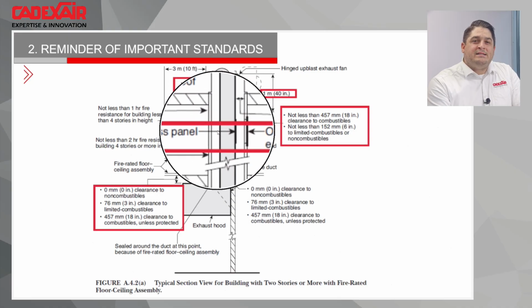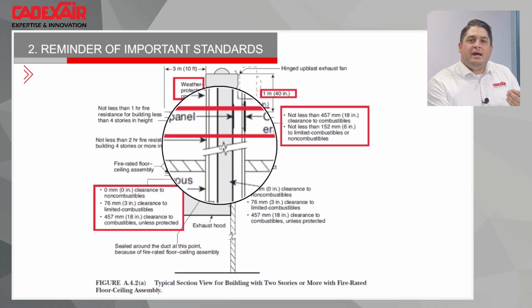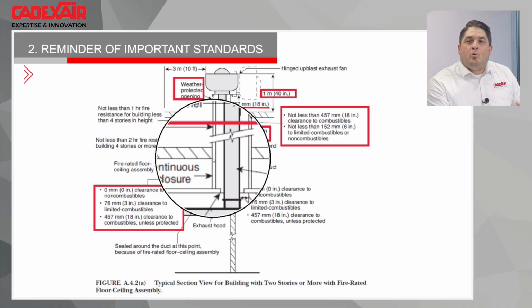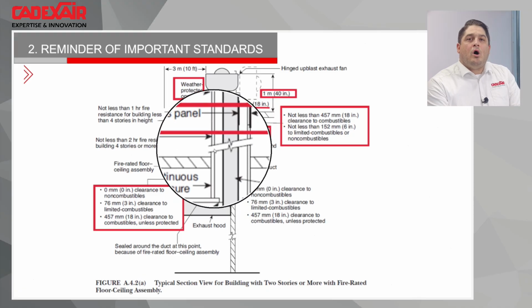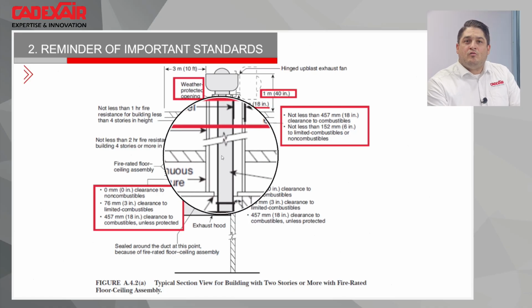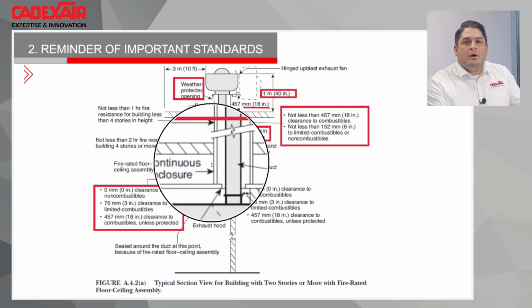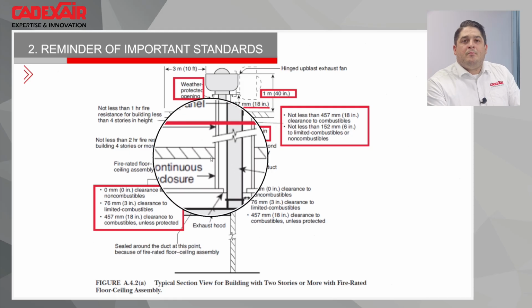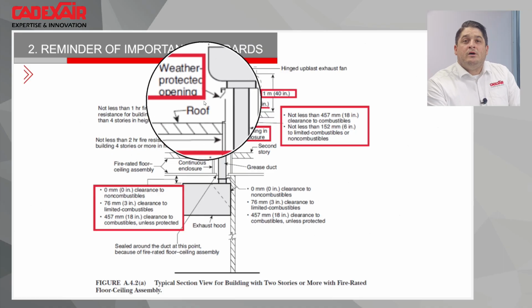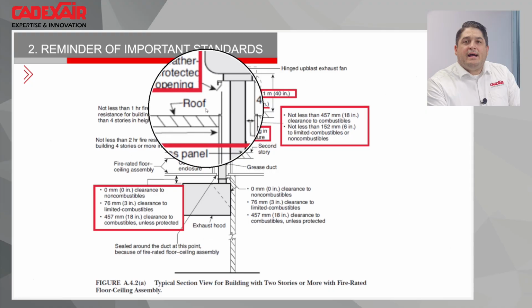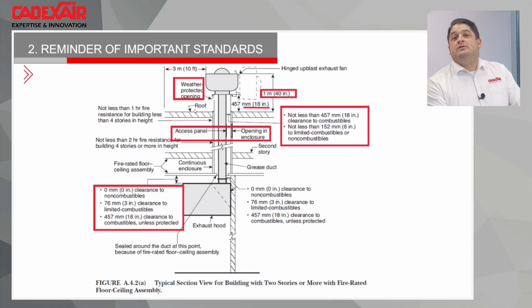The main reason why is that when you're in your shaft and sadly you have a big fire, the duct, with a bit of grease, gets hot, becoming red. So all the heat will dissipate inside the interstice between the ductwork and the fire enclosure. Normally the heat will go up and go up and go up, to the slab of the building. If it's really against the ductwork and there is no clearance, all the heat will get stuck there, and it will get hotter and hotter, and it could break the firewall or melt the ductwork. So as soon as you have a mechanical shaft, you're supposed to have a vented roof curb. This vented roof curb will allow the excess heat to go outside of the shaft. So that's why they ask you that.